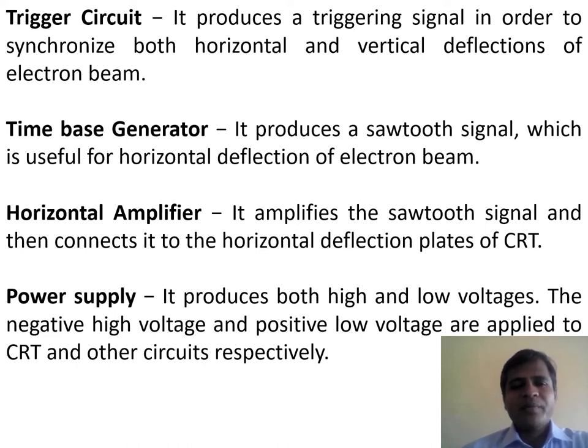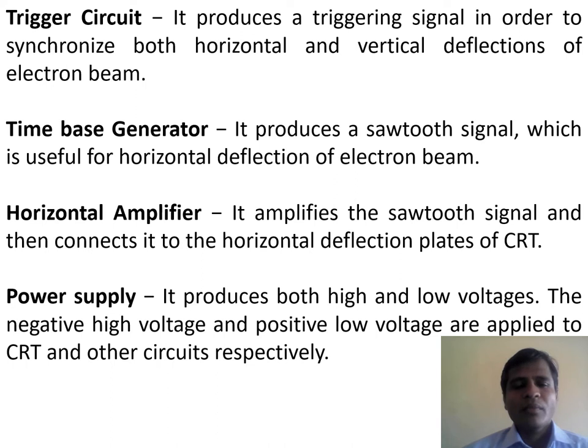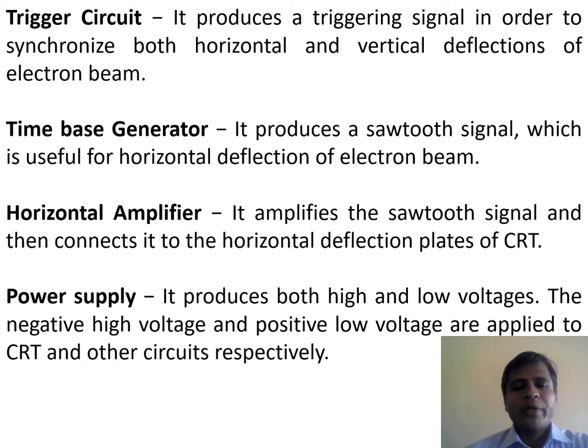The horizontal amplifier performs almost the same basic function as the vertical amplifier, but it amplifies the sawtooth signal and then connects it to the horizontal deflection plates of the cathode ray tube. The power supply produces both high and low voltages. The negative high voltage and the positive low voltage are applied to the cathode ray tube and the other circuits respectively.